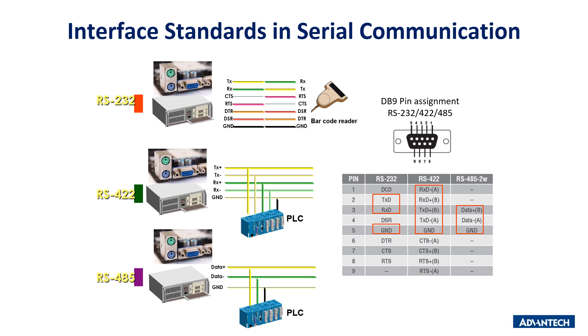In industrial applications, three interface standards are widely used: RS-232, RS-422, and RS-485, typically employing the DB9 connector with nine pins, found in industrial computers as the serial port. RS-232 uses eight of the nine pins for data transmission. RS-422 uses five pins. RS-485 uses only three pins, which represents an advantage over other configurations during equipment installation.